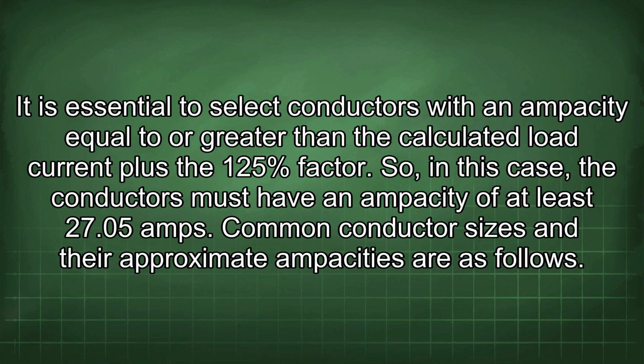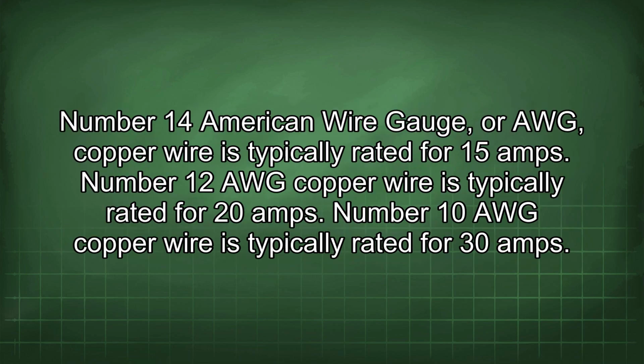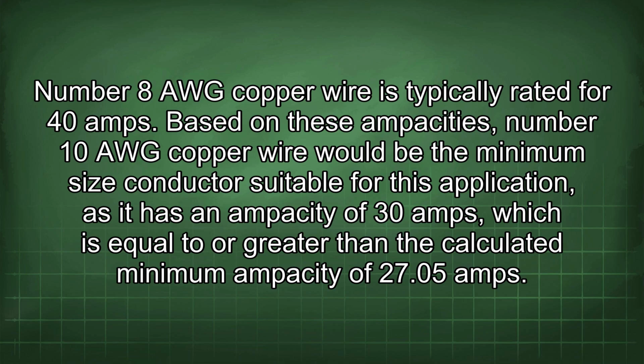Common conductor sizes and their approximate ampacities are as follows. Number 14 American wire gauge, or AWG, copper wire is typically rated for 15 amps. Number 12 AWG copper wire is typically rated for 20 amps. Number 10 AWG copper wire is typically rated for 30 amps. Number 8 AWG copper wire is typically rated for 40 amps. Based on these ampacities, number 10 AWG copper wire would be the minimum size conductor suitable for this application, as it has an ampacity of 30 amps, which is equal to or greater than the calculated minimum ampacity of 27.05 amps.